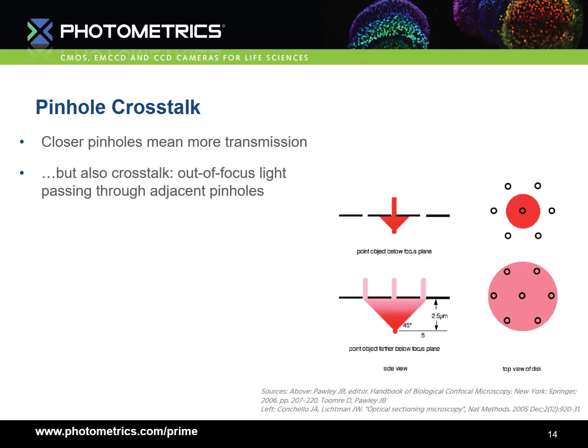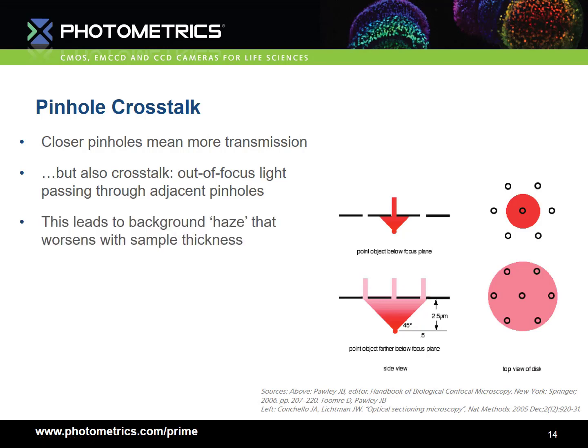Another means of improving transmission of light through the disk would be to reduce the distance between pinholes. However, decreasing the distance between pinholes leads to a problem called pinhole crosstalk. If we imagine for a moment that the pinhole disk is within the same plane as fluorophores, for a slightly out-of-focus fluorophore, this will be blocked by the pinhole disk as we expect. However, for a fluorophore that's sufficiently far from our chosen focal plane, there's a chance that the light emerging from it will enter neighbouring pinholes. This problem obviously worsens the closer pinholes are to each other. For thick samples, this can lead to a background haze, which means our contrast is reduced.